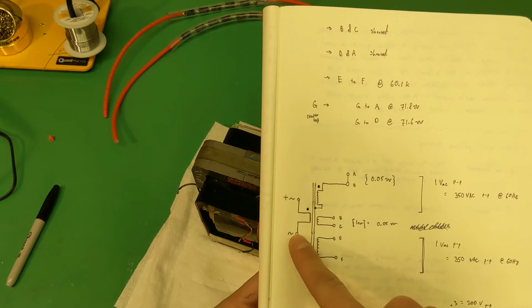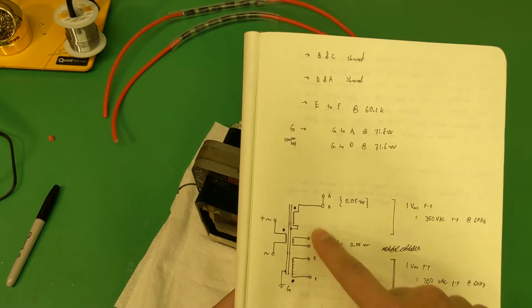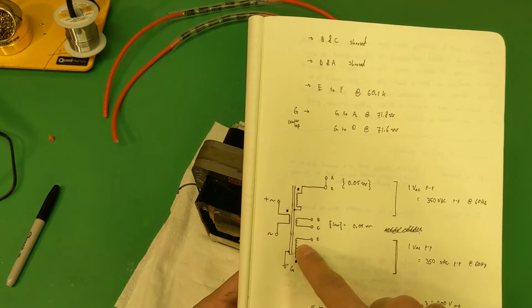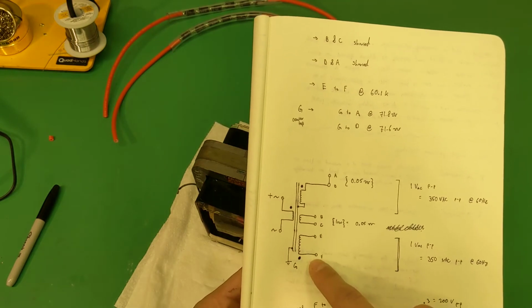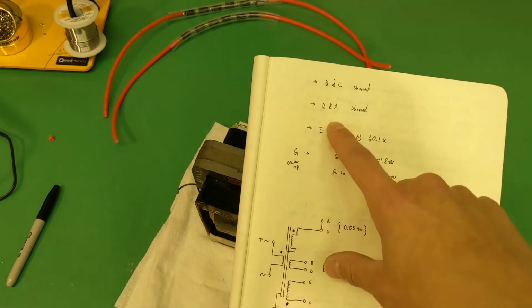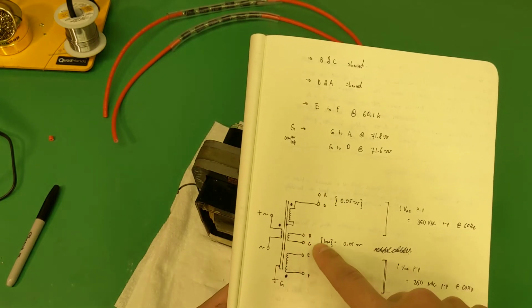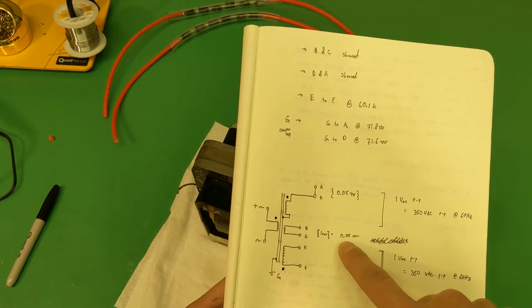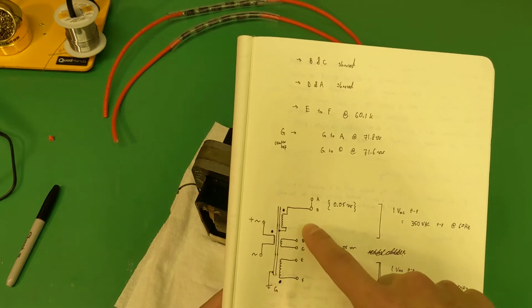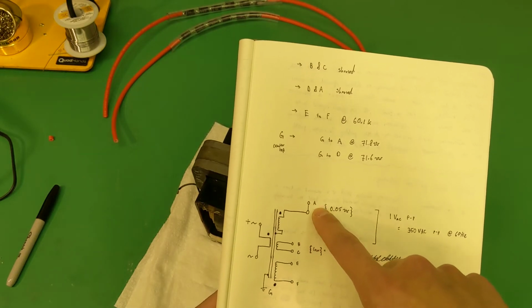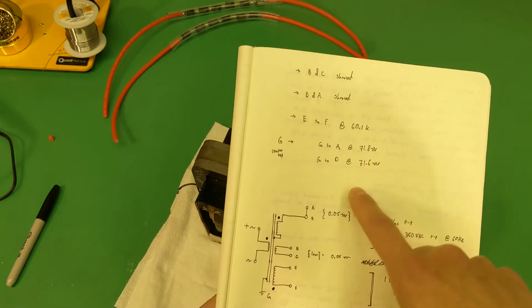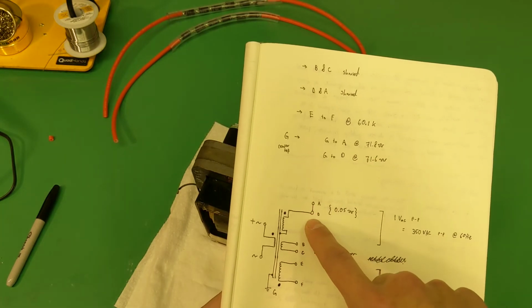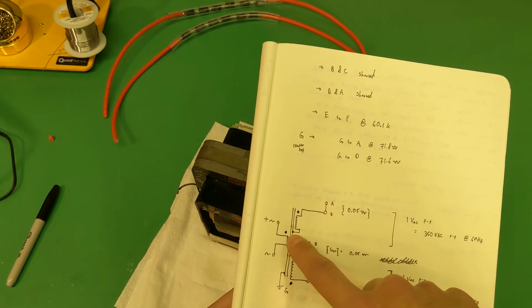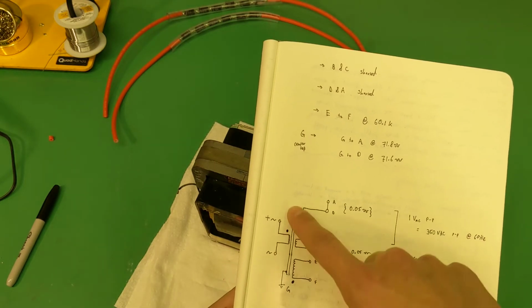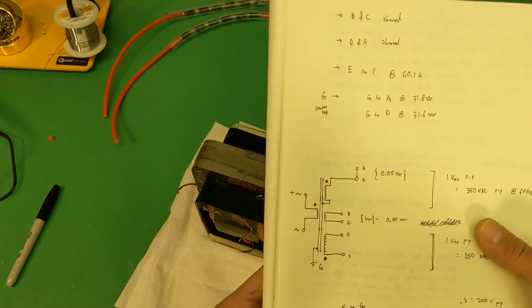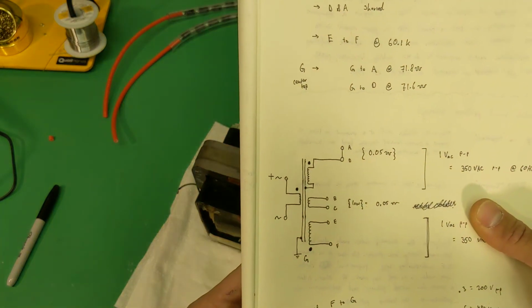We know our two primary inputs. E to F is a separate winding, probably one of the high voltage windings, not connected to anything else. B and C were shorted and don't appear connected to anything else; the resistance was very low, about 0.05 ohms. Then we had this 71 ohm winding, and A and D are both shorted, and G was a center tap connected to the core. So this is, I believe, the wiring diagram for inside this transformer.